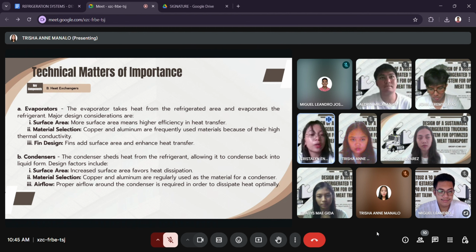Evaporators. The evaporator takes heat from the refrigerated area and evaporates the refrigerant. Major design considerations are surface area, material selection, and fins. In surface area, more surface area means higher efficiency in heat transfer. In material selection, copper and aluminum are frequently used materials because of their high thermal conductivity. Fins add surface area and enhance heat transfer.